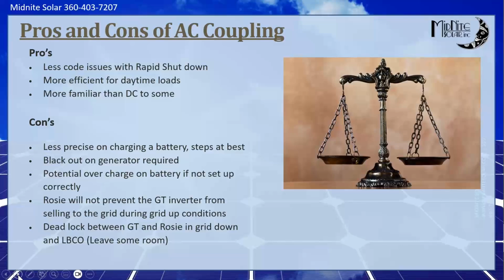If you have a system that is going to be off grid, and that's the whole goal of the system, then some DC coupling really is almost a requirement. You really want some of that controlled charging with that finite control. If the system is only there to back up the beer fridge during a power outage, then we're not quite so concerned about how we treat those batteries, because the batteries are probably going to die of old age before we wear them out, because normally your power outages are 2 or 3 times a year, right? And they don't last very long, maybe 5 times a year. So the battery is going to age out before you physically wear it out like you would in an off-grid situation. So there's a couple different ways you can look at that, and we'll talk a little bit about that in the sizing.